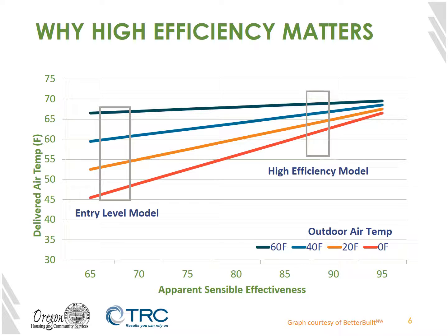So we have to ask ourselves which of these systems is most likely to deliver comfort to the building during that cold winter month. Research in Canada actually shows that models with lower ASEs are more likely to be shut off by homeowners and tenants in their buildings due to the pure comfort issue. And if we go through the trouble of spending the money to make sure we have a balanced ventilation system, we really want to ensure that it will not be disengaged by the tenants. This becomes a bigger deal as our codes get better and as we make our buildings more efficient, because it really becomes critical that we meet our ventilation requirements.